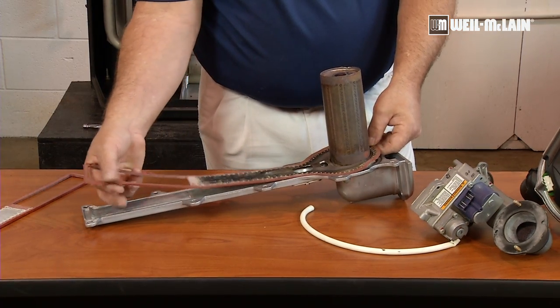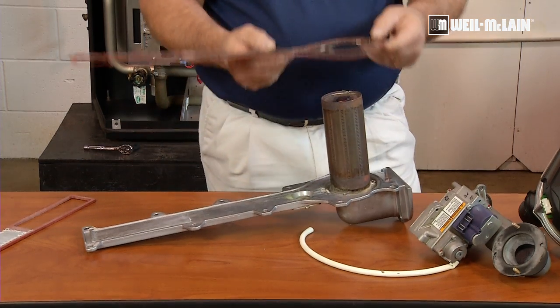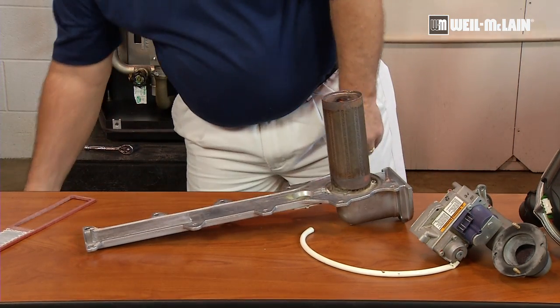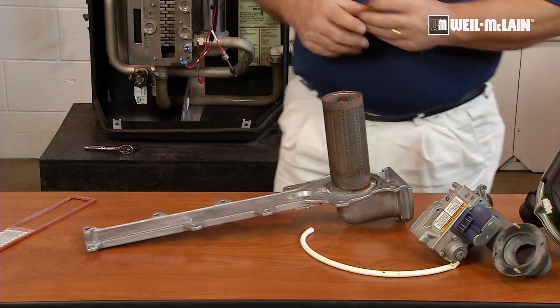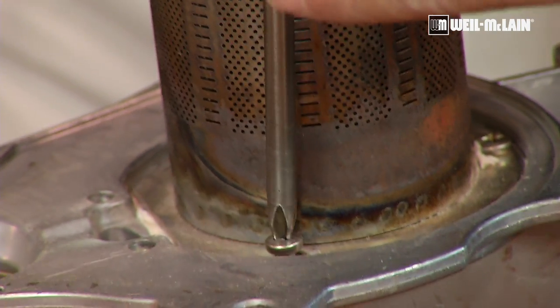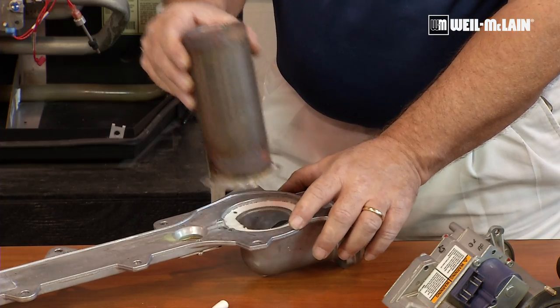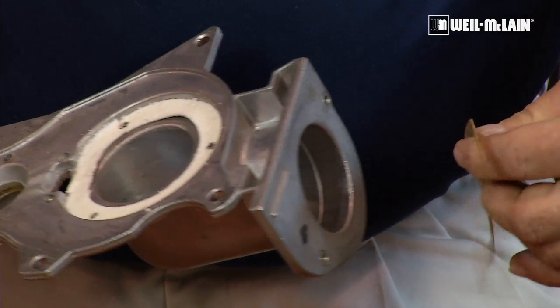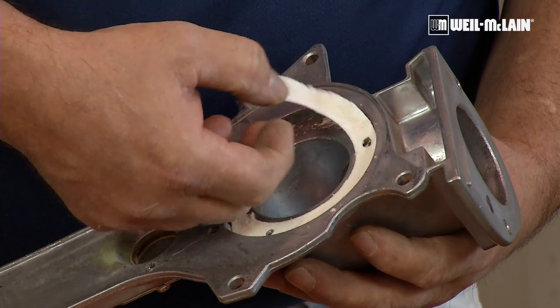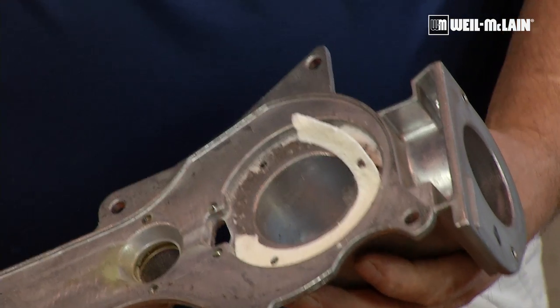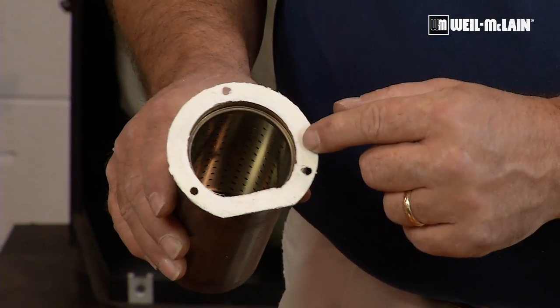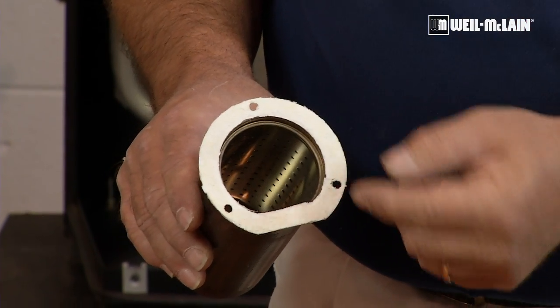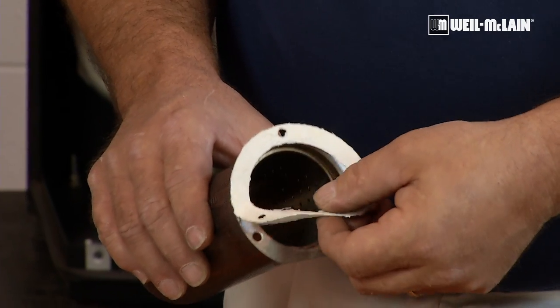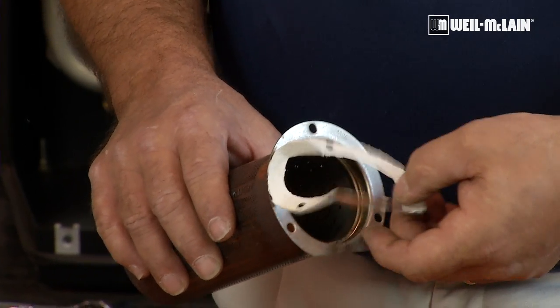You can see this is wet. I'm going to remove that, discard it. Now the burner is held on by three Phillips head screws. So I'm going to remove the old gasket material, both the cork gasket and the Ceraphelt gasket, from the cover plate. I need to remove the residue from the gasket material from the flange of the burner. Now on this, if we do it gently, it should come off in one piece.